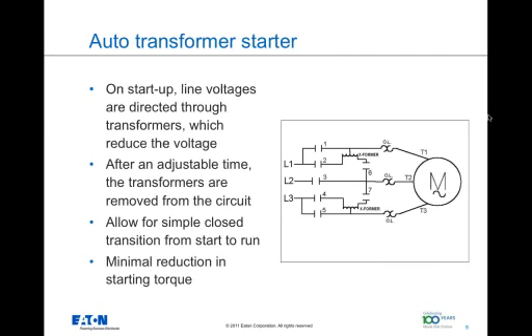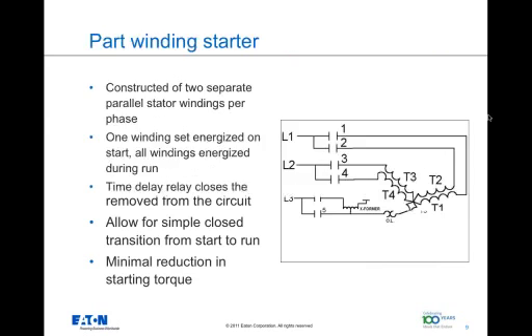And now, what is an auto transformer starter? This device basically uses an auto transformer to reduce the current that is drawn from the power line. It may have multiple taps stepped through by multiple contactors to achieve the desired soft start. This device is somewhat unique in that, because of the transformer action, the torque the motor develops is consistent with the line current levels, and it provides the best level of starting torque per starting amp, but at the cost of several current bumps at each contactor transition. So for the most part, you do get the reduced voltage play. However, it's not as smooth as a solid-state soft starter is going to give you. The second one in the series is the part winding starter.